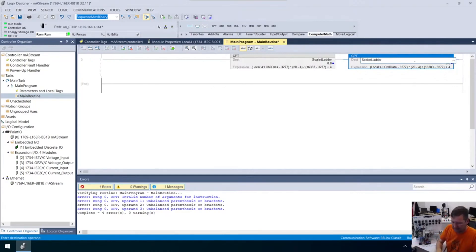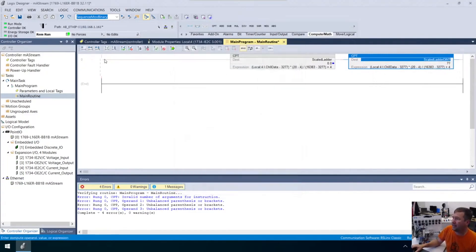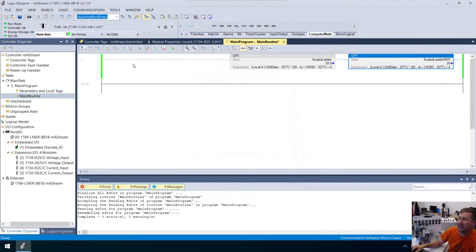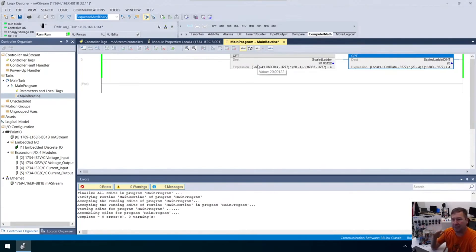So I'm going to make a second one of these — this will be D-I-N-T. I'm just going to create that and leave it as the default. Matthew asks: in the SLC file in RSLogix 500 there was an SCP instruction — scale with parameters. In Studio 5000 there isn't; you do use the compute. But stay tuned because in function block, yes, we do have a scale instruction, and that would typically be my preferred way to do it.